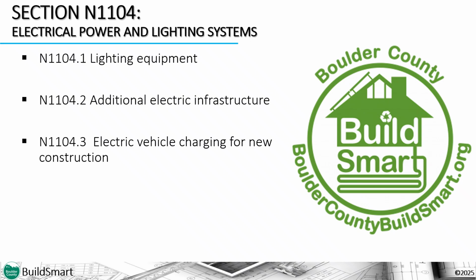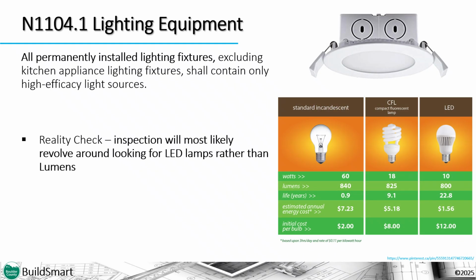Our last section of mandatory items is the electrical power and lighting system requirements that are listed on this slide. They are within what we would call Section R404 of the 2021 IECC or Section N1104 of the IRC. Where in the past only a percentage of the lighting in a house had to be efficient, now all installed lighting is required to be high efficacy lighting. In reality, this means LED lamps should be installed everywhere except in appliance lighting applications.